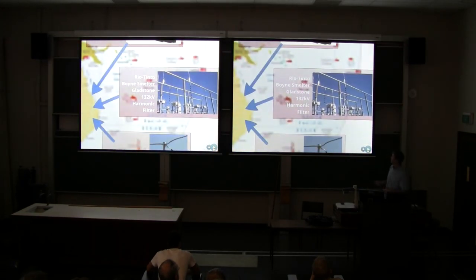This is another site. In this case, they wanted to expand their capacity—expand their high voltage network outside the plant—but they had no room to put in conventional CTs. So they asked, can we fit optical CTs in here? They managed to squeeze them in, basically suspended from the existing structure, and this way they didn't take up any room in the substation. So this is another benefit of the optical technology.